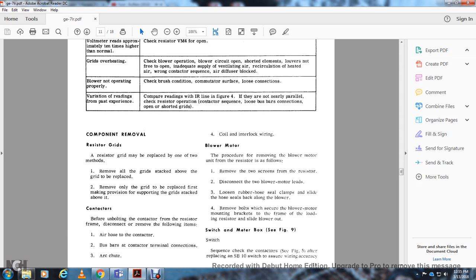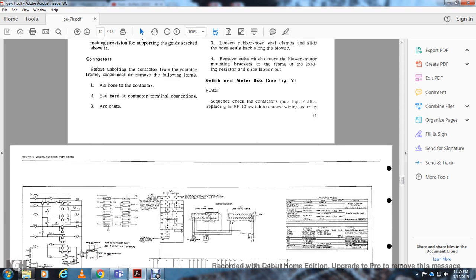1 Remove the screen from the resistor. 2 Disconnect the 2 blower motor leads. 3 Loosen the rubber hose and seal clamp. Slide the hose seals back along the blower. Remove the bolts securing the blower motor mounting brackets to the frame of the loading resistor. Slide the blower out. Switch and meter box, see figure 9 switch. Sequence check with the contactors, see figure 5, after replacing SB 10 switch to ensure the wiring is correct.